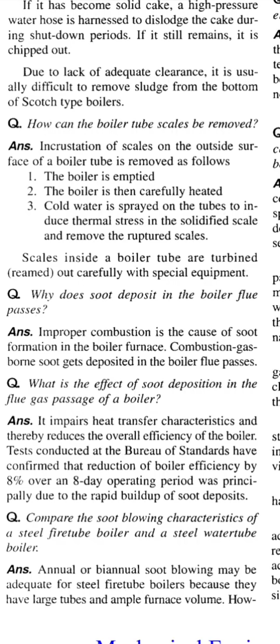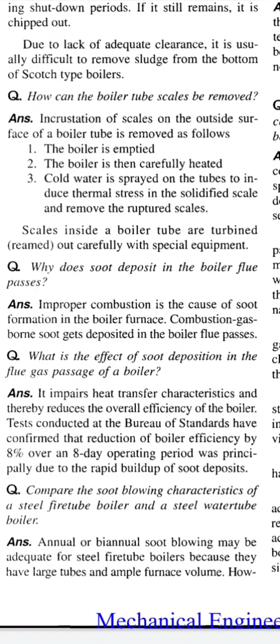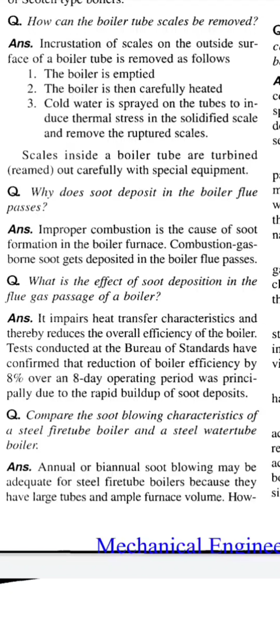Question: why do soot deposits form in the boiler flue passes? Answer: improper combustion results in soot formation in the boiler furnace. Combustion gases carry the soot, which gets deposited in the boiler flue passes. Question: what are the effects of soot deposition in the flue gas passage of a boiler? Answer: it impairs heat transfer characteristics and thereby reduces the overall efficiency of the boiler. Tests conducted at the Bureau of Standards have confirmed that a reduction of boiler efficiency by 8% over an 8-day operating period was principally due to rapid buildup of soot deposits.